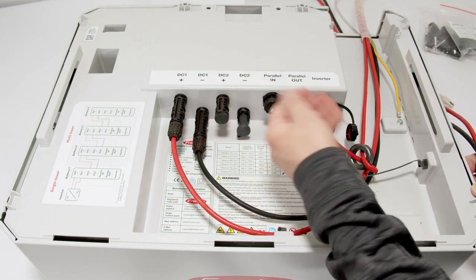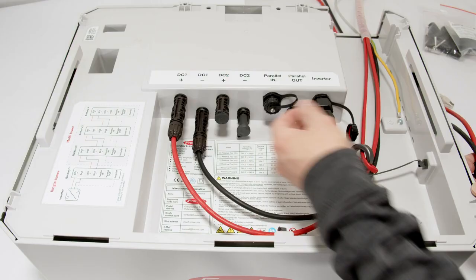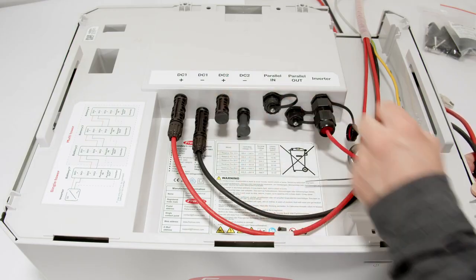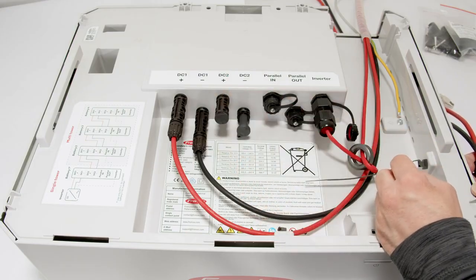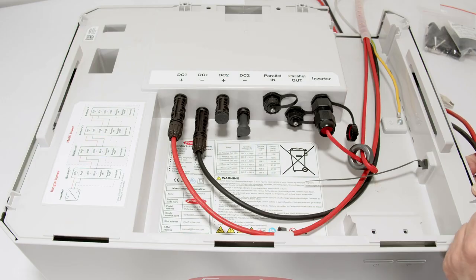Please note that within the first battery, the parallel in contact stays open. So there is no termination plug that comes inside here, you just leave it open as it is. To do the termination on this data communication, you need to open up the debug port that is on the right hand side beneath the cover. We will do this afterwards to activate or deactivate the termination resistance on each and every battery system.